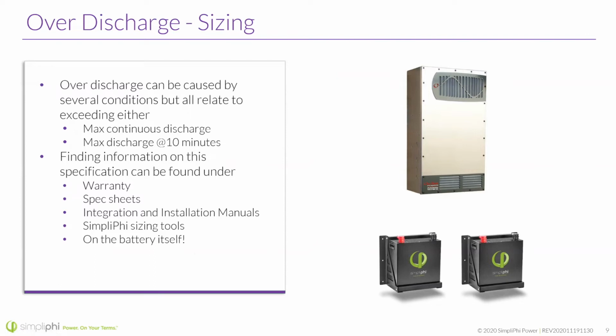And really, actually, we can even claim 5, but we don't run 8,000 watts continuous out of this inverter. There's some efficiency loss, so 4 batteries is the minimum. That can be found in their integration guides. If you look around in there, you'll find sizing references specific to different products. So maybe it's a Schneider or an Outback or a Sol-Ark. You'll find that different sizing.